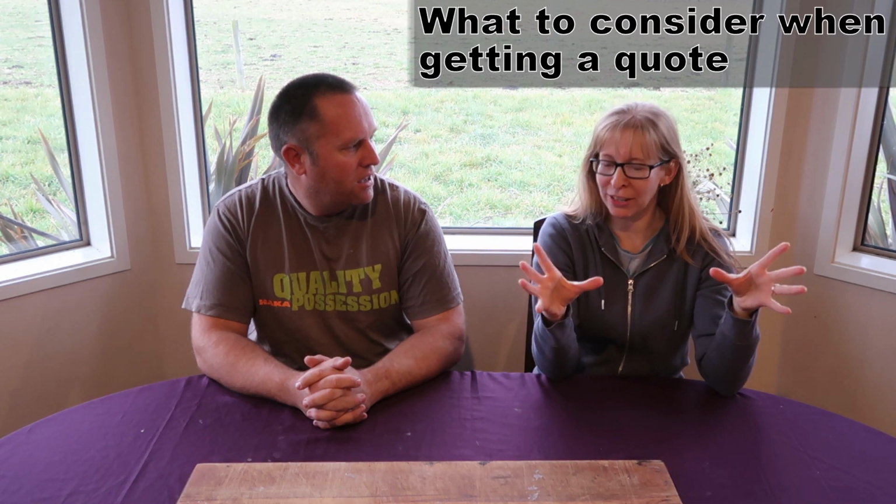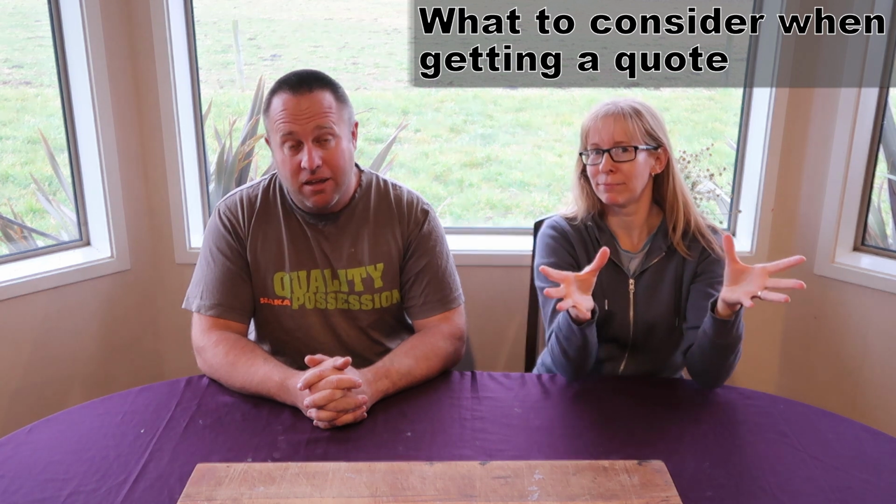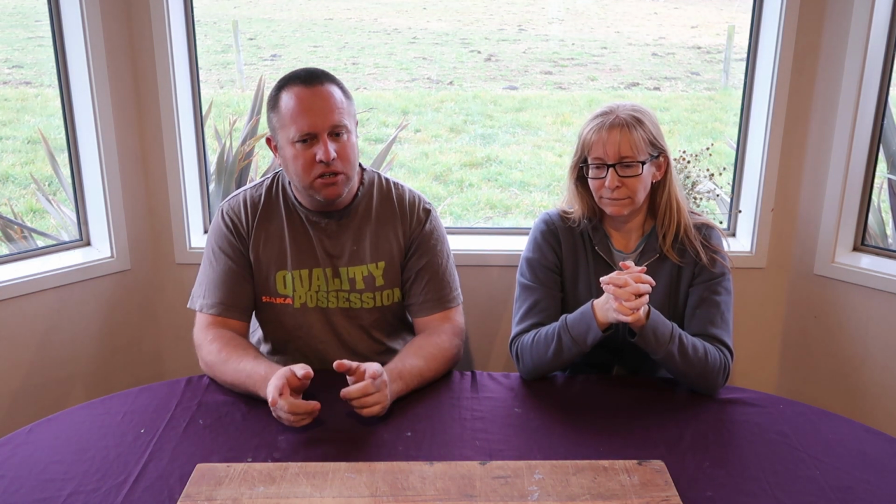If you're getting a company to quote for putting in an aircon, just bear in mind they could be trying to quote a cheaper price to get the install, and they could be undersizing the heat pump, so it could end up costing more. This is actually another video all on its own, but we'll touch on it because it is a genuine concern. I'm always brutally honest. I always size it 20% bigger than it has to be, because if it drops to 0, a lot of units will actually lose 30% of their capacity, and if it's already borderline not big enough when they put it in, as soon as you get cold, it's not going to work.